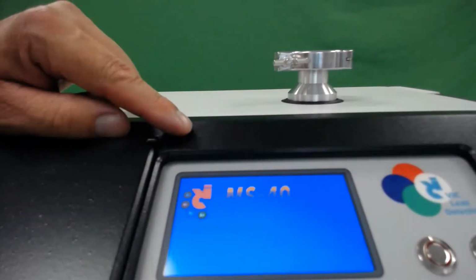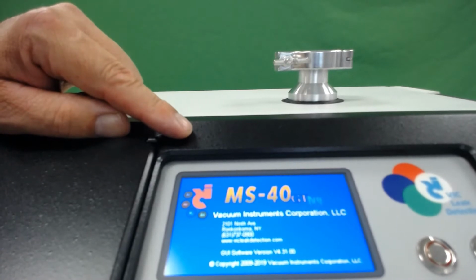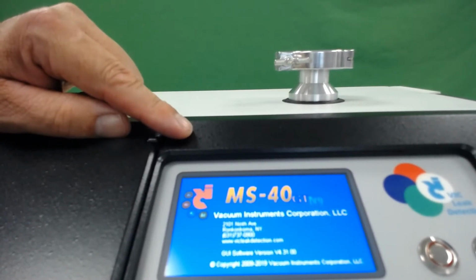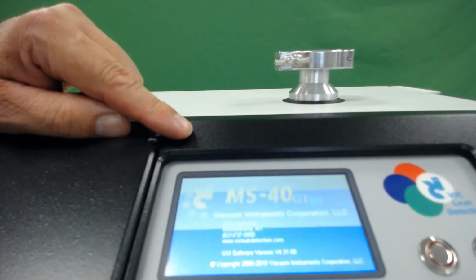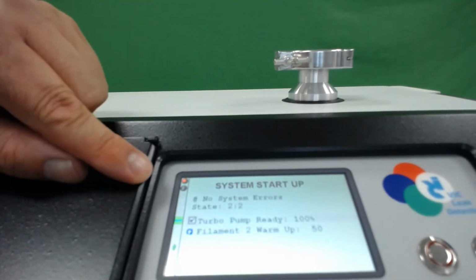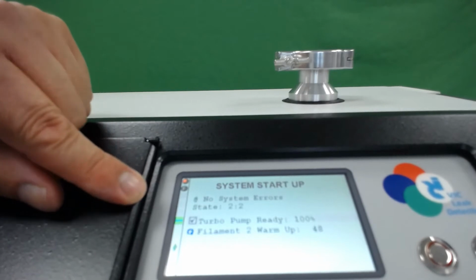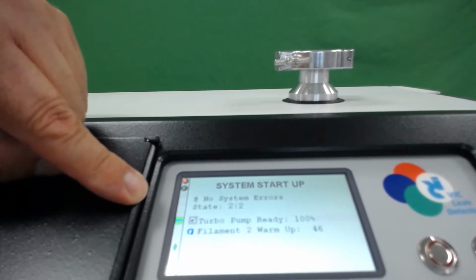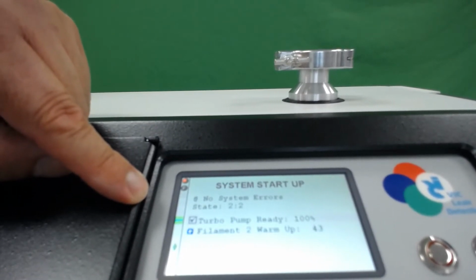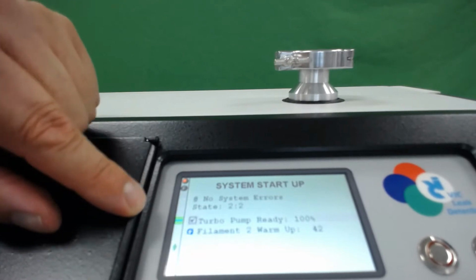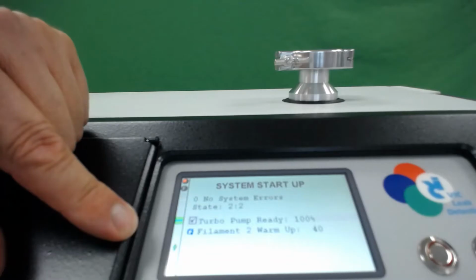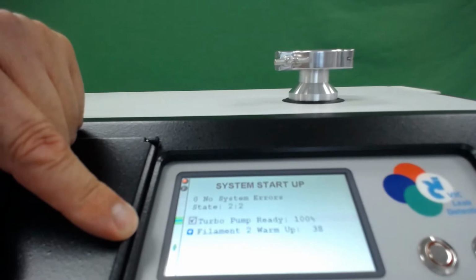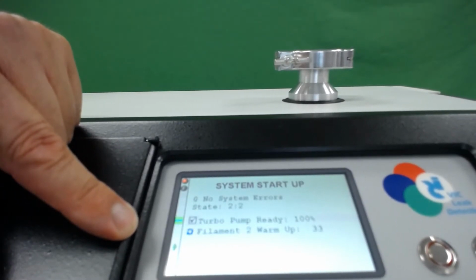Once the power switch is turned on, the MS-40 will load its program and will begin starting the unit up. The turbomolecular and foreline pump will turn on. The machine is showing you no system errors. We're monitoring the state condition as the machine gets the vacuum pumps operational. Tells you the turbo is ready. We're in a filament warm-up period, and at the completion of the filament warm-up period, we'll begin a background acquisition.